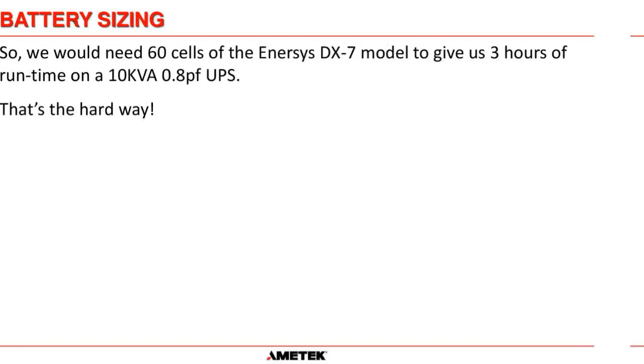Most of the battery manufacturers have a sizing tool that you or a rep can use. Basically, you type in all the information. I did it for this battery here: I put in that it was a UPS down to 1.75 volts per cell, the load of the UPS was 10 kVA with a power factor of 0.8 and an inverter efficiency of 0.88, and it calculated the load kilowatts required to be 9.09, just like I did manually. For the DX range, it says it's good and gives you a 20.3% margin, so you've got 20% more power than you actually need.